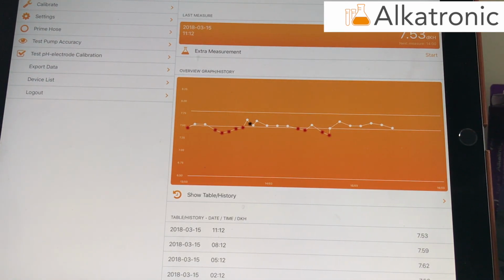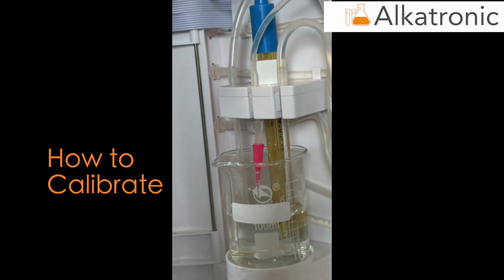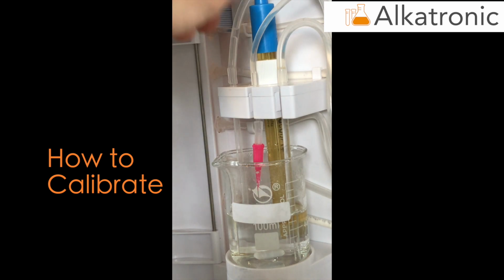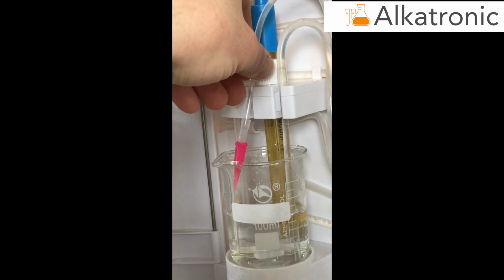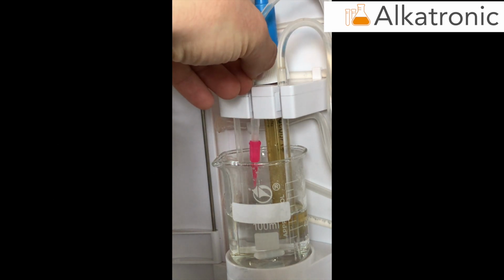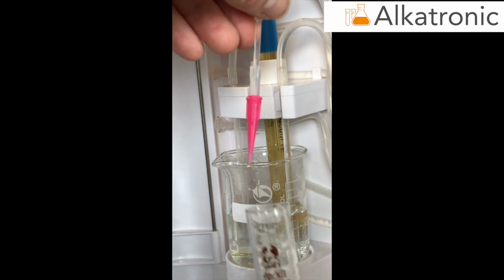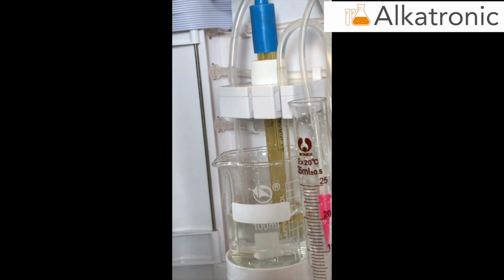Now I will give you a short instruction on how to calibrate the pumps, as that is a regular maintenance and it is very easy. And that is actually the only thing you have to do to control and manage this machine once you have set it up. Open the front door, of course, and then you take the pipe from pump C. It's a very easy and smart clicking function, so you can easily take it out. And you put it down in the measure vial, the small measure vial of 25 milliliters.